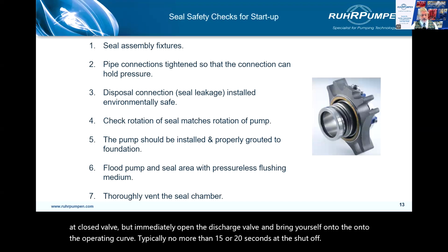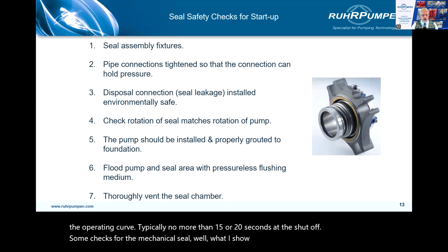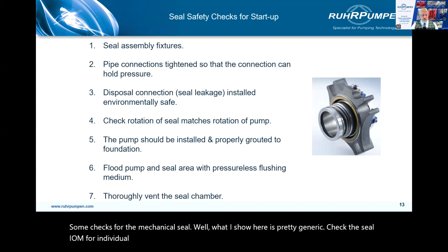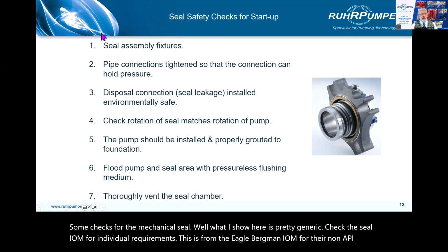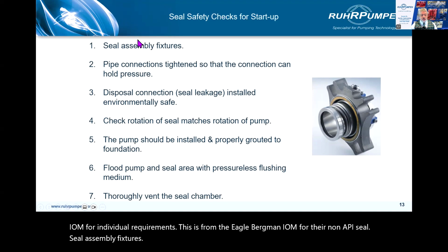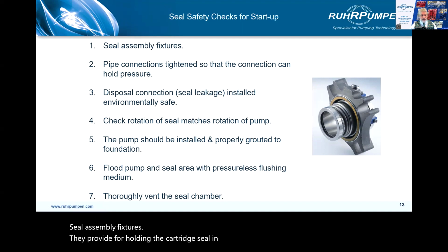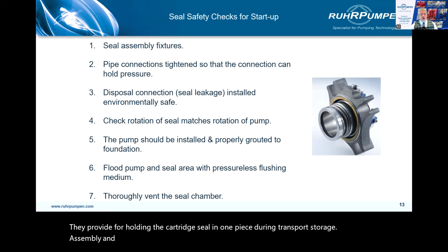Some checks for the mechanical seal. Well, what I show here is pretty generic. Check the seal IOM for individual requirements. This is from an Eagle Burgmann IOM for their non-API seal. Seal assembly fixtures provide for holding the cartridge seal in one piece during transport, storage, assembly, and removal. They must be removed before startup.